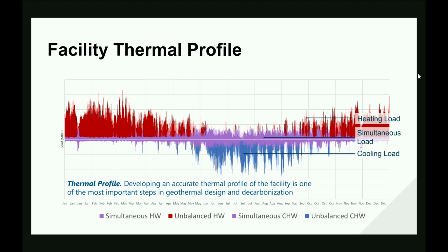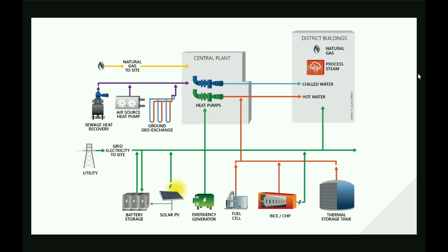That was one of our biggest learning items at Ball State University, my first large campus conversion. We had to order the heat pumps all at once because they got federal money, and we ordered four 2,500-ton units based on their steam profile. Today they run one machine. That's way oversized, and that's not good for a chiller, plus a lot of upfront cost they didn't have to pay for. It just shows you how inefficient steam is, by the way.